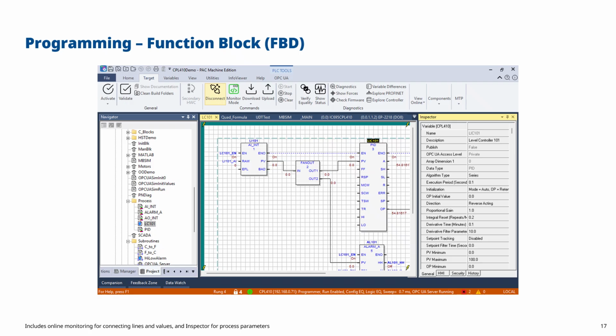Now with the function block diagram, again I'm online, so I can see the values of the parameters which I'm connected to. So for example, LC101EN is the enable input, and you can see that's on. And then I've got a level indicator, LI101AI, and you can see the raw AI value there is 0. And then you can see I've got a variety of blocks. So I've got an analog input block, which has got an associated set of parameters called LI101. So that's my level indicator.